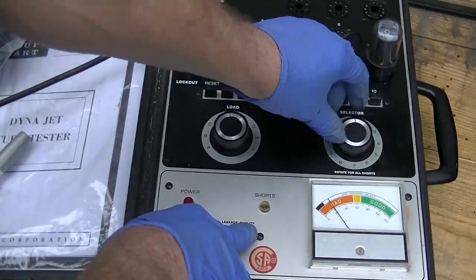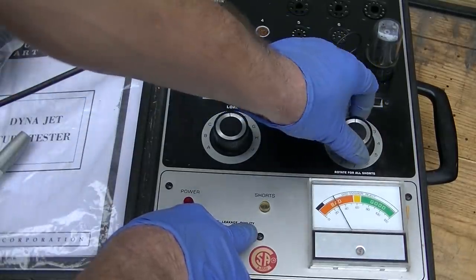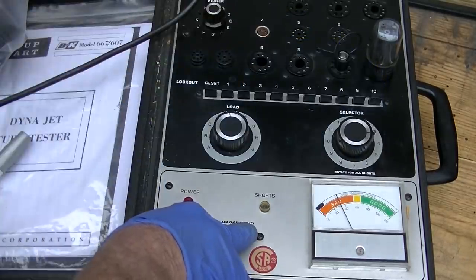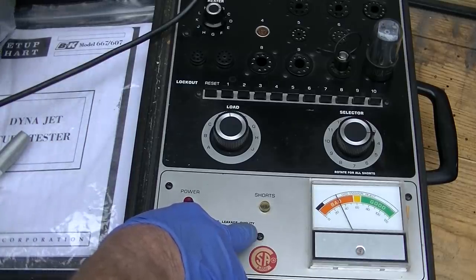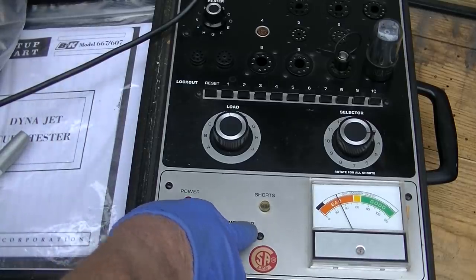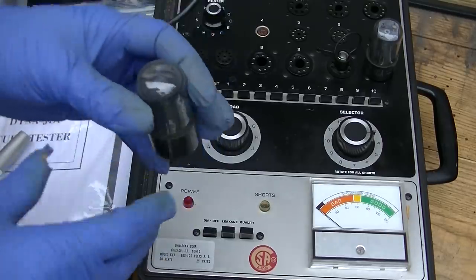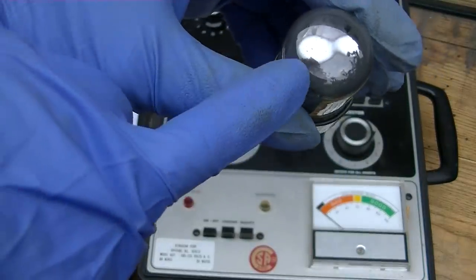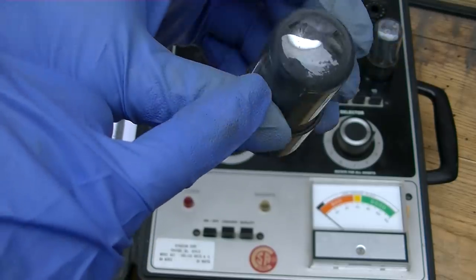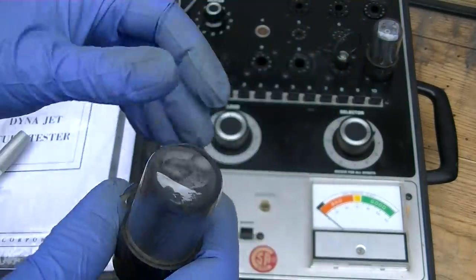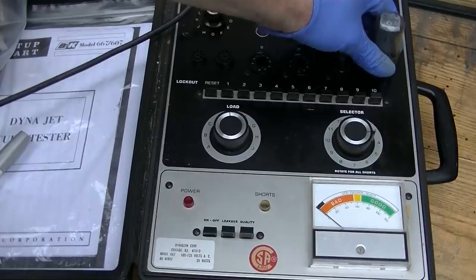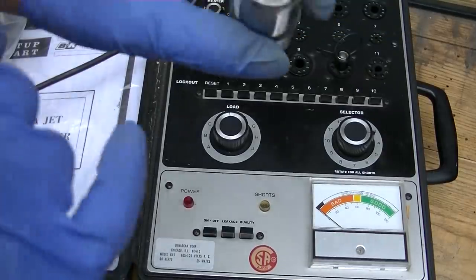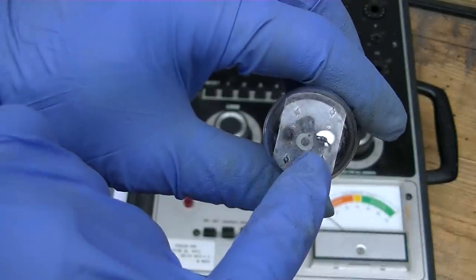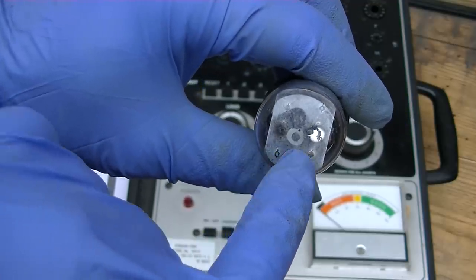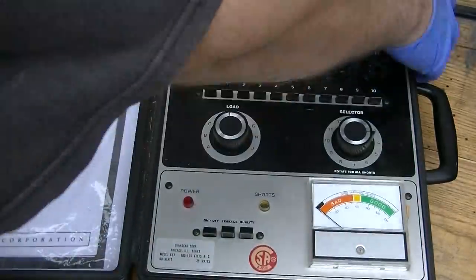That one's a little bit on the weak side. And you can tell by the filament burn off, these marks here, that's tungsten evaporation from the tube being used. So the higher hours, and you can see that some of them have more burn off on one cathode than the other.